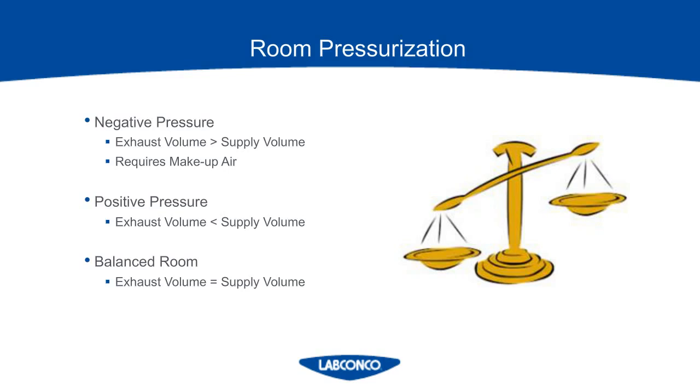For example, let's say it's summertime and you turn your fume hood blower on and it suddenly becomes very warm in the room. This means the room is too negative — it's warm because all of the air conditioned air is being exhausted from the lab, meaning there is not enough makeup air being supplied to the room. So before I get into all of the fume hood talk, I want to make sure we all know that when more air is exhausted from the room than supplied to it, it's negatively pressured. Conversely, when more air is supplied to the room than exhausted, it's positively pressured. These basic rules give you the building blocks for what we need to know for the rest of the presentation.